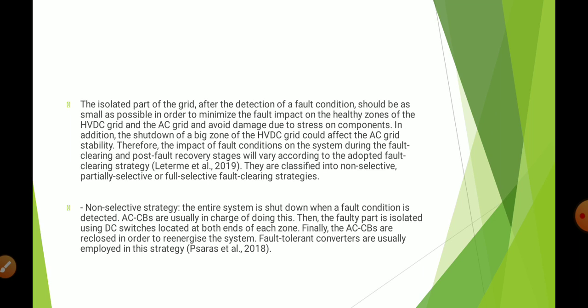The isolated part of the grid after the detection of a fault condition should be as small as possible in order to minimize the fault impact on the healthy zones of the HVDC grid and the AC grid, to avoid damage due to stress in the components. In addition, the shutdown of a big zone could affect the AC grid stability. Therefore, the impact of fault conditions on the system during the fault clearing and post-fault recovery stages will vary according to the adopted fault clearing strategy. They are classified into non-selective, partially selective, or fully selective fault clearing strategies.